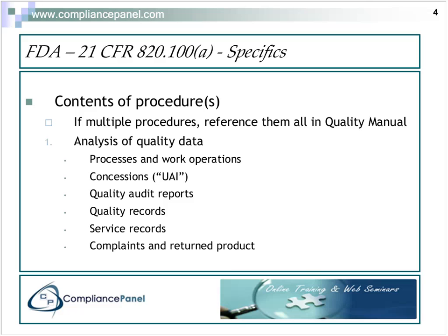Concessions, something that many people often forget or more often overlook with regard to corrective and preventive action, is concessions. Use as is. There are many times where you have a component or a yield from a process that does not meet your specification. However, the area of the specification that is not met is, for example, cosmetic. Let's say that you have a piece of hardware that is supposed to be powder blue, but it's navy blue instead. From an efficacy perspective, that is completely acceptable to use. From a sales perspective, it may not be.